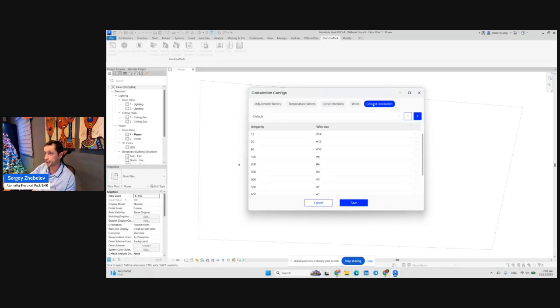Ground conductors: there are rules for defining them. In the National Electrical Code in the United States, it depends on ampacity. In Europe, it depends on hot wire size. So we also need to know about this, and it will be possible for an engineer from the United States or from Europe to create rules for defining ground conductors.